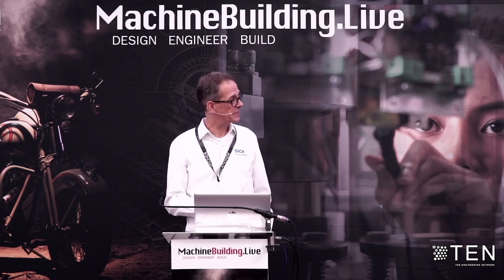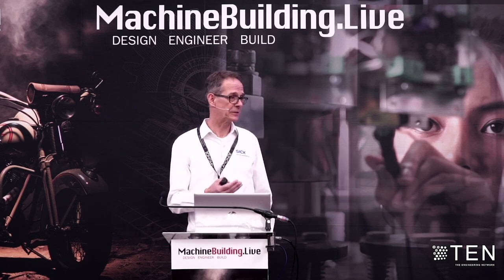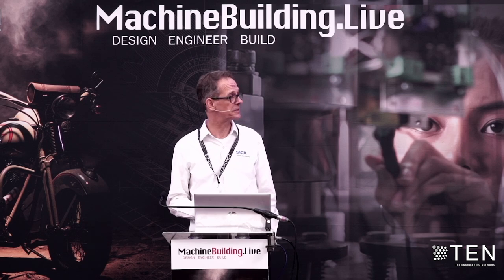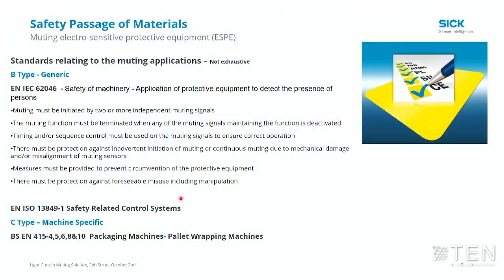The standard I've picked out, which is most succinct when we look at the requirements of muting systems, is EN IEC 62046. The key points of this standard are muting must be initiated by 2 or more independent signals that are triggered by the materials moving through the light curtain or other ESPE.